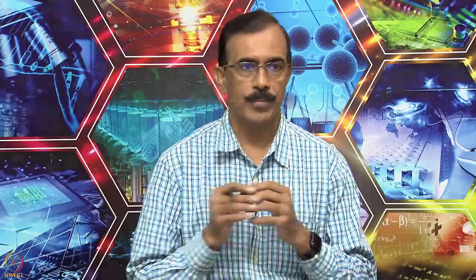Ultraviolet spectroscopy involves the measurement of absorption of light in the visible as well as the ultraviolet region. The visible region is 400 to 800 nanometers whereas the UV region is around 200 to 400 nanometers. This essentially involves the absorption of light by the substance under investigation. Since the absorption of light involves the transition from one electronic level to another, that means an electronic transition, UV spectroscopy is also known as electronic spectroscopy. To record the UV spectrum, the given compound is dissolved in a suitable solvent and the solution is placed in a quartz cell of path length 1 centimeter.